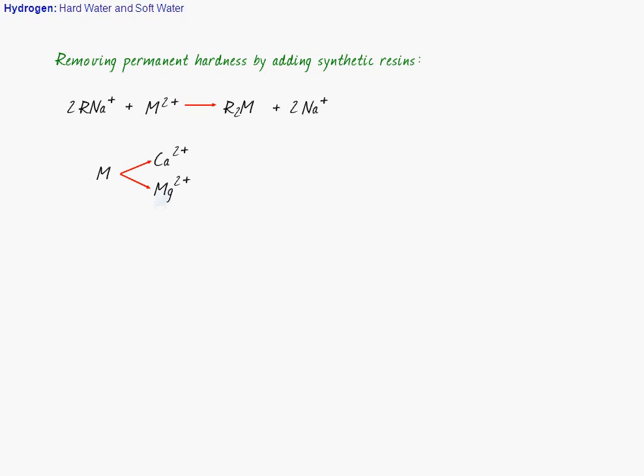In the first exchange, hydrogen ion exchanges for calcium ion, Mg2+, sodium ion and other cations present in water, and it becomes acidic. In the next exchange, anions like Cl-, SO4 2-, HCO3-, etc. are replaced by OH-, which neutralizes the hydrogen ion set free in the first exchange.